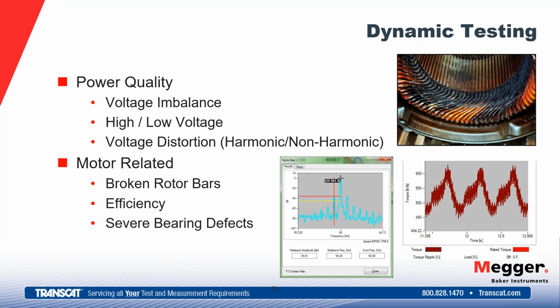So that motor is going to become more inefficient, and it's going to cause higher heating in the motor. So now we're degrading that insulation at a faster rate. The dynamic testing and dynamic motor monitoring can alert us to that.